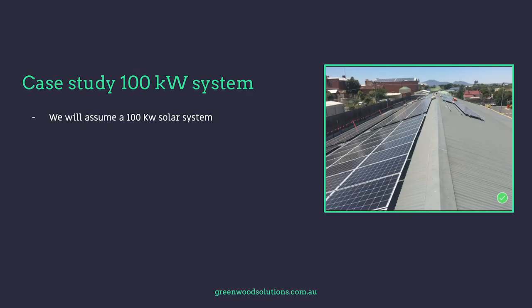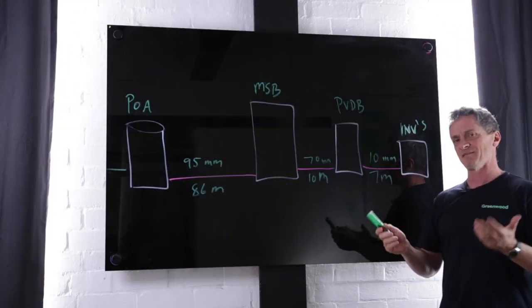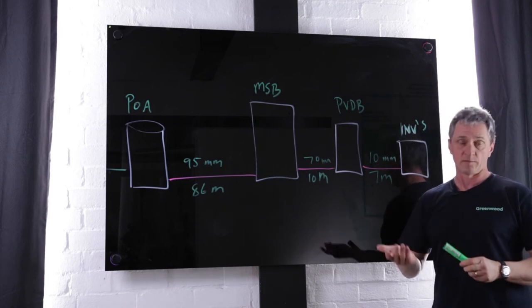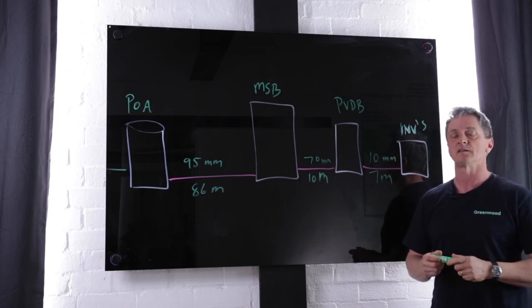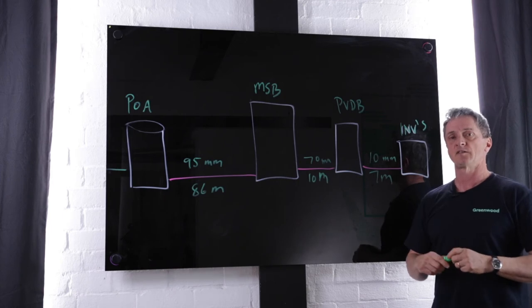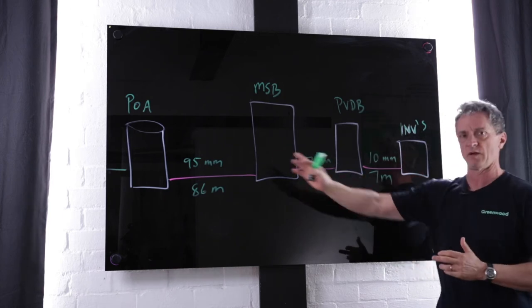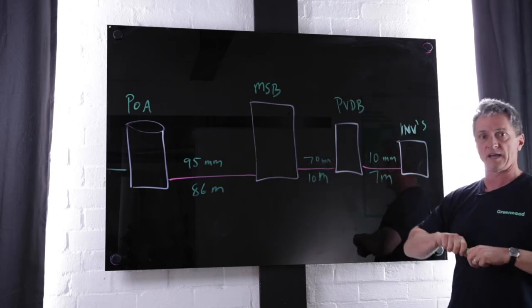We'll assume a 100 kilowatt solar system — that's 100 kilowatts of inverter capacity on the AC side — and in this case we're going to use four 25 kilowatt inverters just to make things easy. Remember: 400 volt nominal for three phase commercial solar, two percent means eight volts to play with over the entire length.